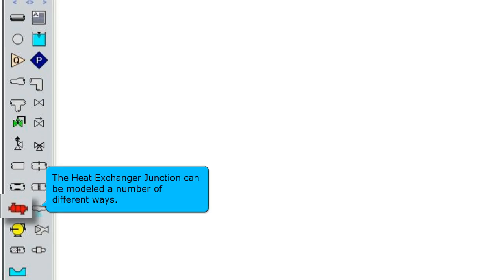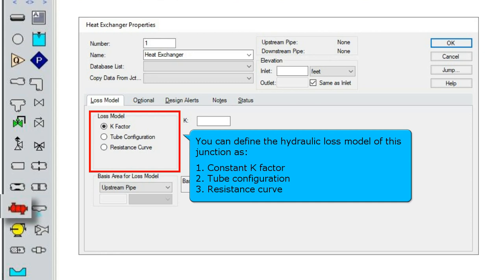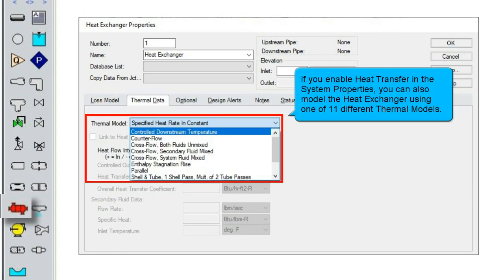The heat exchanger junction can be modeled a number of different ways. You can define the hydraulic loss model of this junction as a constant k-factor, a tube configuration, or a resistance curve. If you enable heat transfer in the system properties, you can also model the heat exchanger using one of 11 different thermal models.